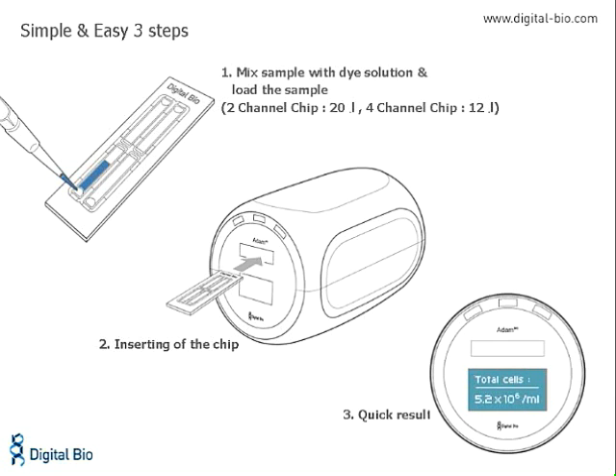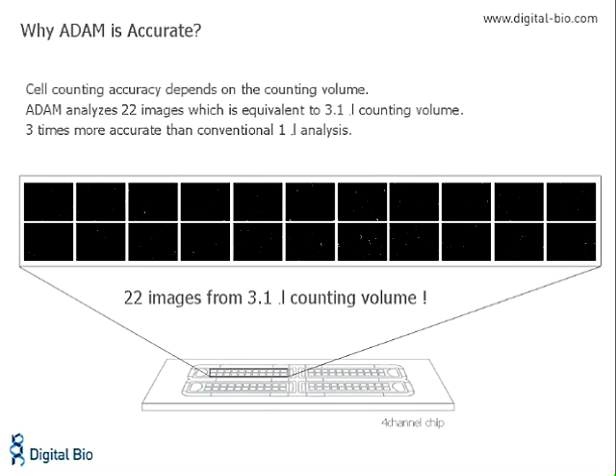The workflow provided by ADAM couldn't be simpler. Cells are mixed with a propidium iodide staining solution and loaded onto the chip. The chip is inserted into the carry mechanism, and within 90 seconds a cell count is generated. ADAM's accuracy derives from the relatively large volume assayed. ADAM scans 22 fields in each chamber, representing a total volume of 3.1 microliters. In comparison, hemocytometers use only 1 microliter.